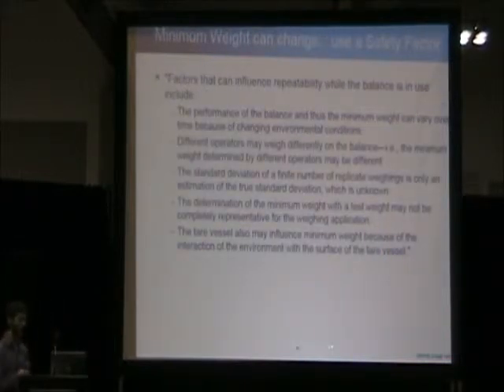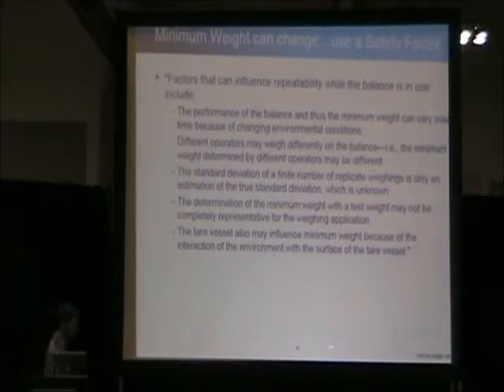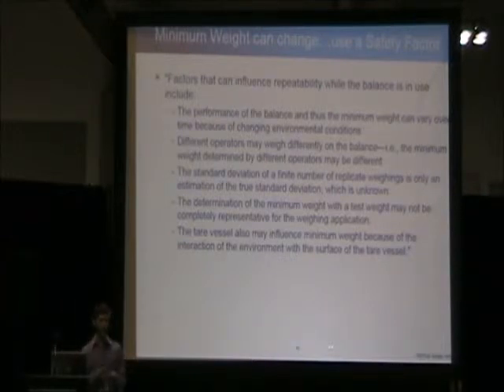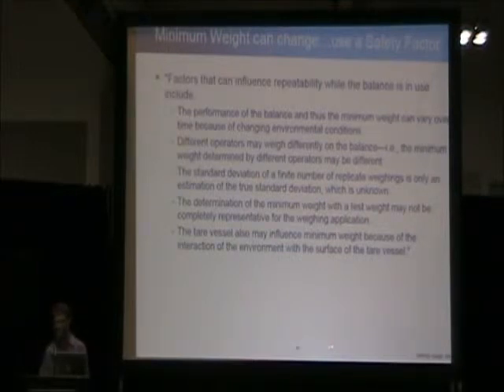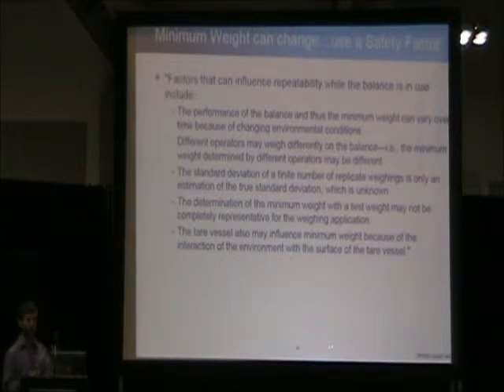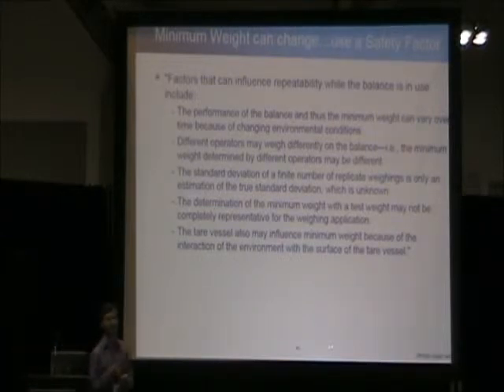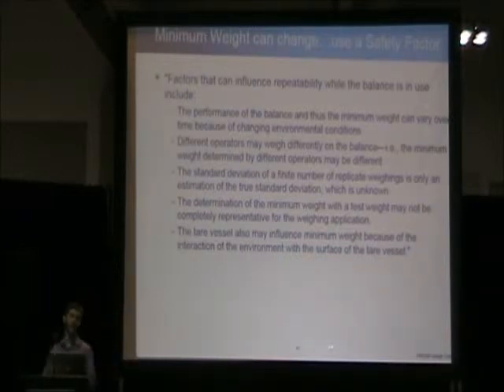Now, let's talk about the concept of a safety factor. When I say safety factor, what I mean is that when you establish your minimum weight, which again, for let's say a technician coming into your facility, they would be performing a repeatability test. They would be using that equation that I presented prior, and you'd be getting a particular weight value. So let's say that your minimum weight on a 5-place analytical balance is 30 milligrams. You tested it in June of this year.